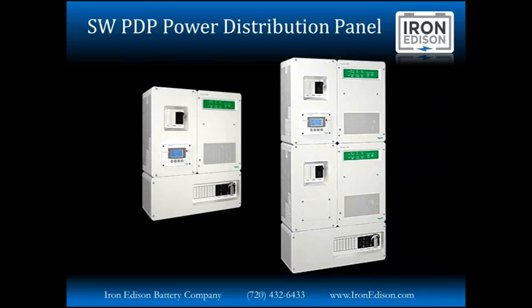Here's a couple pictures of a fully integrated system, obviously with 1 or 2 SW inverters. It's also worth noting, if you look closely on the power distribution panel, the Conext system control panel is mounted inside the power distribution panel, making for a very nice, elegant installation. And of course, if you have a dual inverter situation like you do on the right, you have space for another accessory, maybe a battery monitor, that could be mounted in there as well.